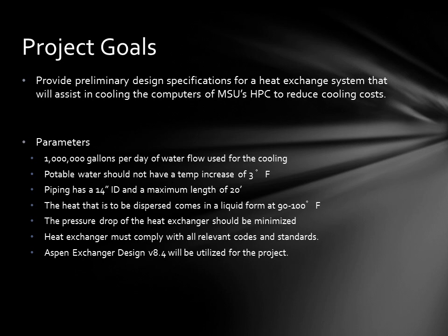Some of the most important parameters we used were to ensure that the pressure drop of the heat exchanger should be minimized, and that the potable water should not have a temperature increase of more than 3 degrees Fahrenheit. We also used Aspen Exchanger Design for this project, as the program is ideal for design optimization.